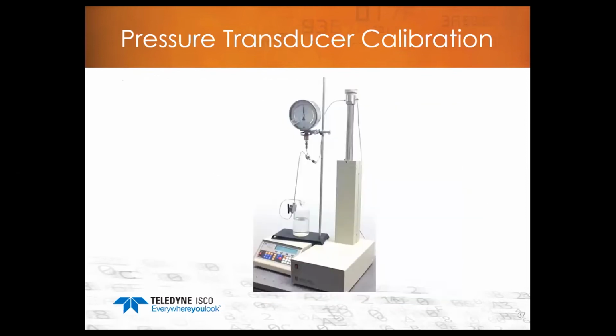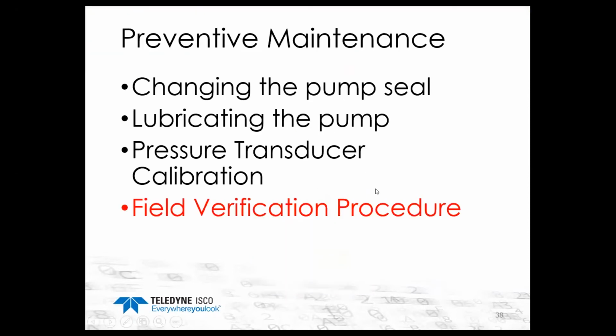And this is just a setup that we would maybe use back in our service area. We have our external gauge. We have our source, and you want to test it with water. So we have our external pressure gauge connected to the pump, and then the other port of the pump would be plugged off, because basically you're going to be running the pump in a constant pressure mode with the pump basically dead-ended. It's not going to be pumping anywhere downstream. You're just going to be building pressure inside of the pump with the external pressure gauge connected to one side of the pump.